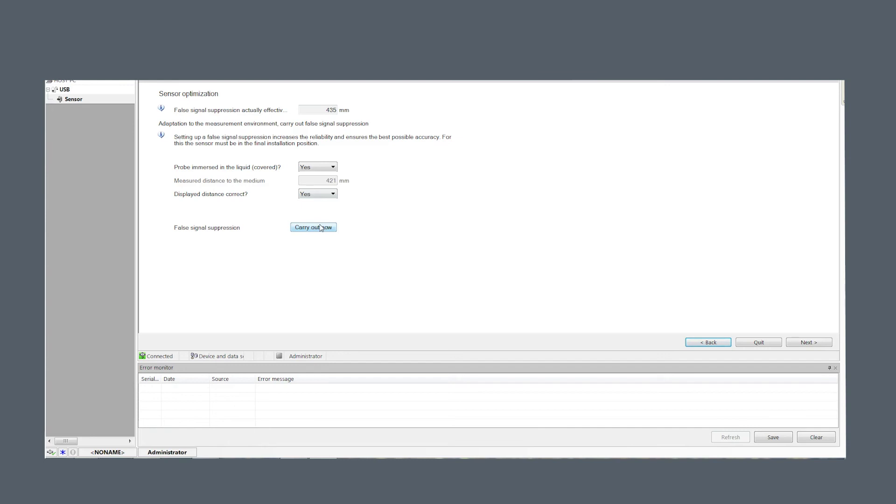When probe is not immersed, suppression should be carried out to probe end. False signal suppression is best performed if probe is uncovered or when level is low and a major portion of rod or cable is not immersed in liquid.